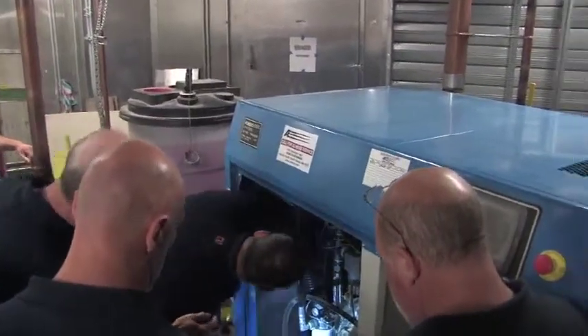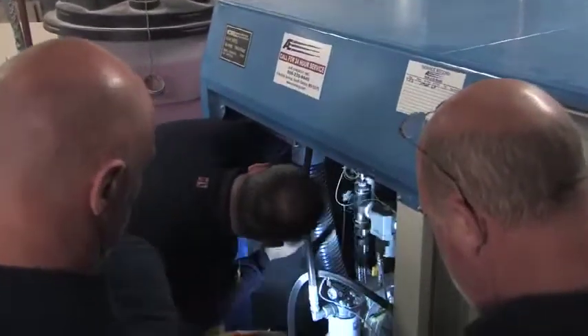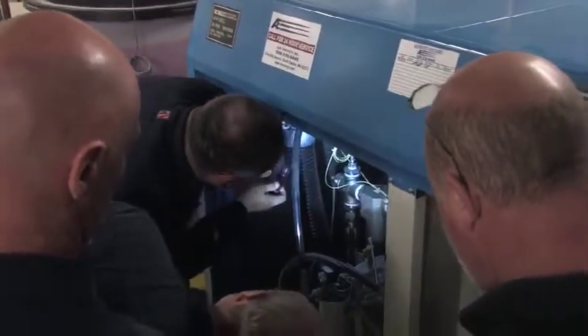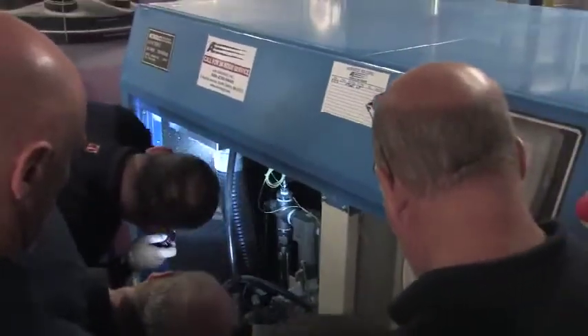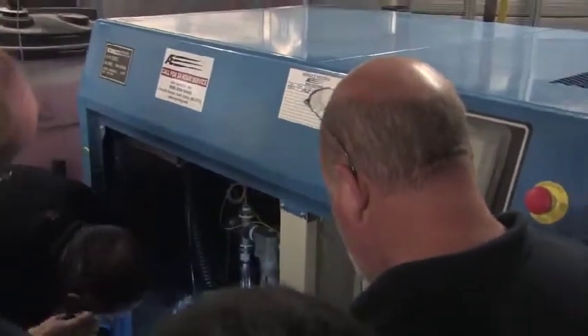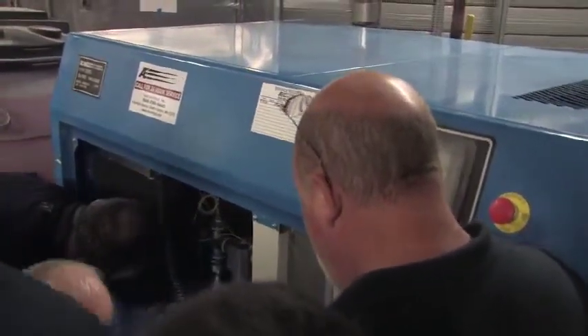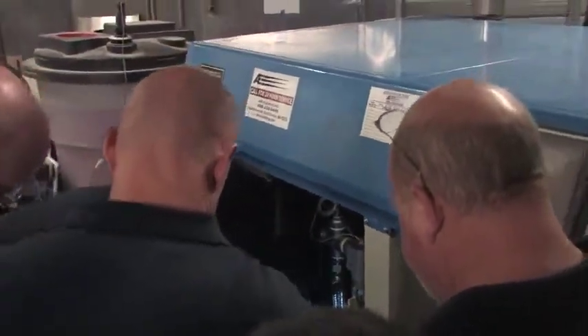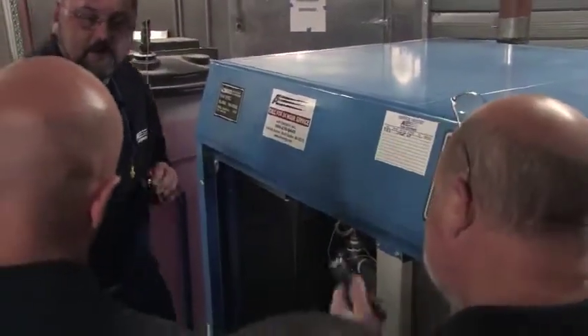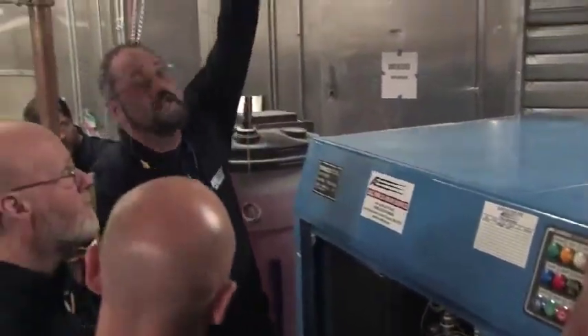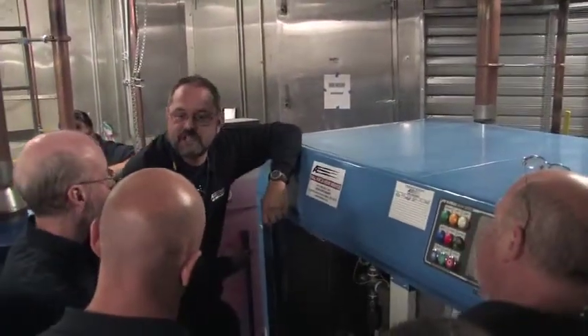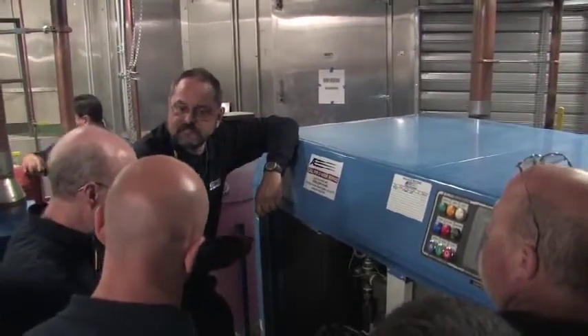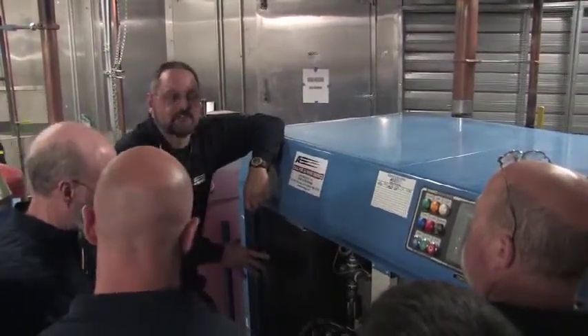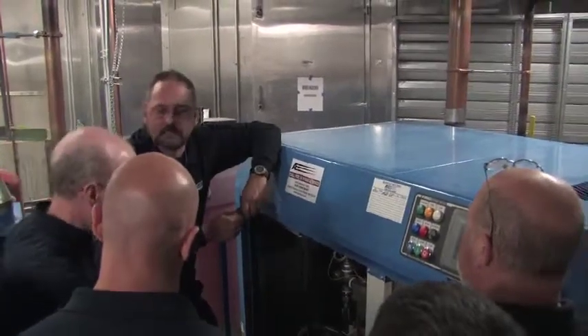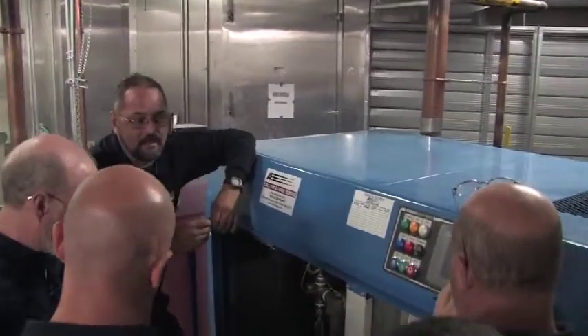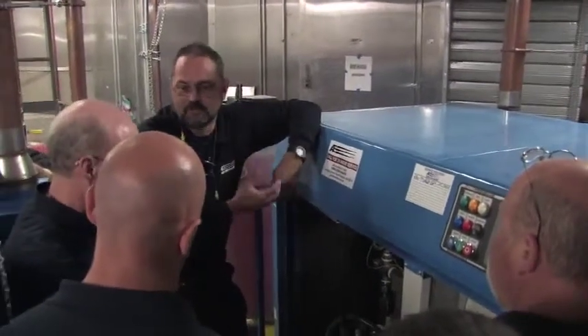The inlet pressure sensor is actually, here's the temperature sensor. That's inlet temperature. The inlet pressure sensor is actually mounted down below here, one of these lines on the bottom, coming off here in the base. Because the inlet pressure sensor is doing two things. It's telling you what's coming down here, but it's also telling you how much restriction you have across the filter. So even if you've got plenty of flow coming down the pipe, if the filter gets real dirty, that's going to give you some kind of warning pointing at the air filter.